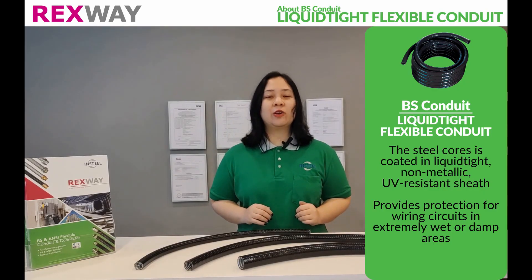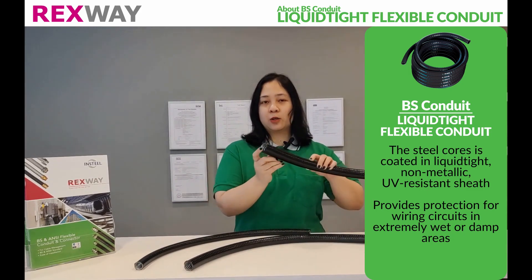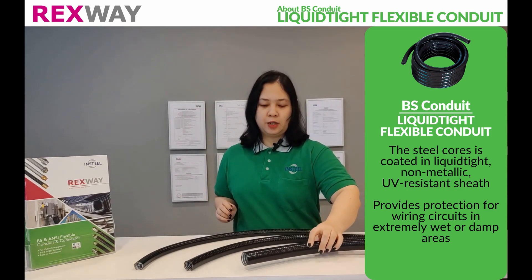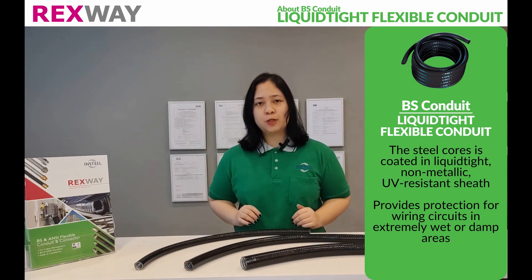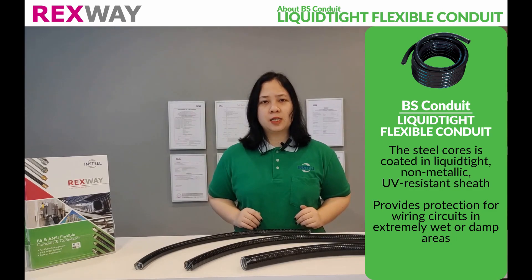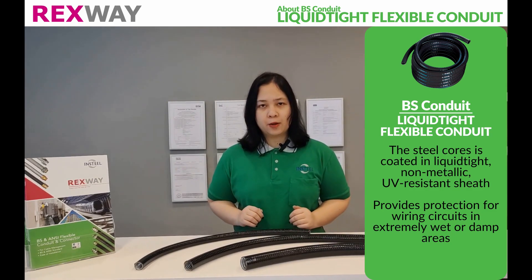Rexway BS Liquidtight Flexible Conduit has a steel core that is coated in a liquidtight non-metallic UV-resistant sheath. It is intended for use in wet locations or where exposed to mineral oil, providing protection for wiring circuits located in extremely wet or damp areas.